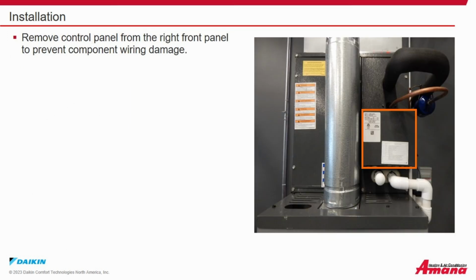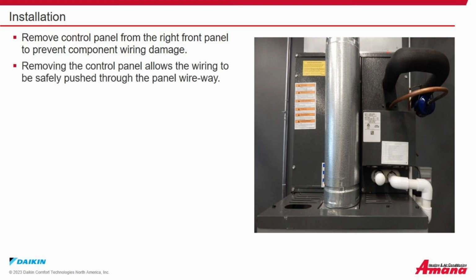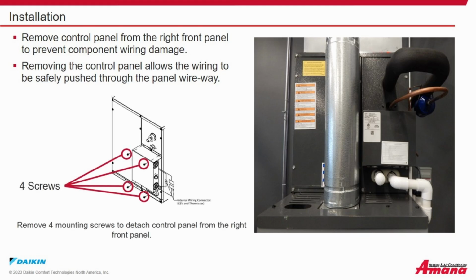Remove the control panel from the right front panel of the coil to prevent component wiring damage. Removing the control panel allows the wiring to be safely pushed through the panel wireway. Remove the 4 screws to detach the control panel from the right front panel.